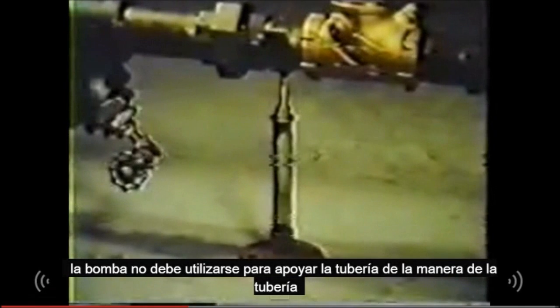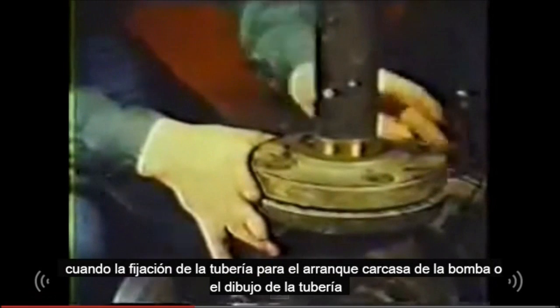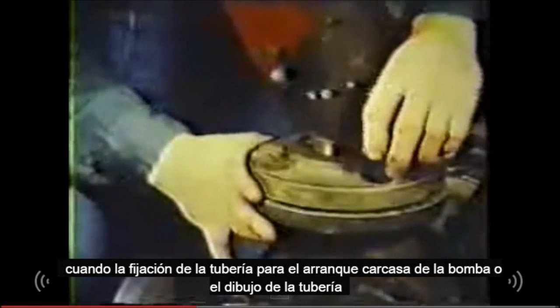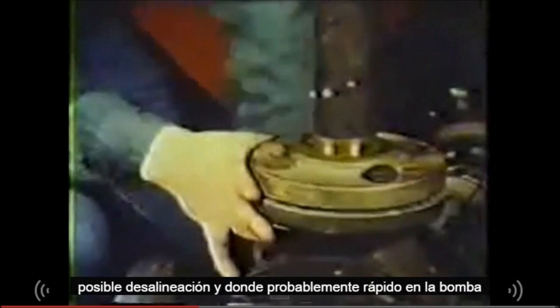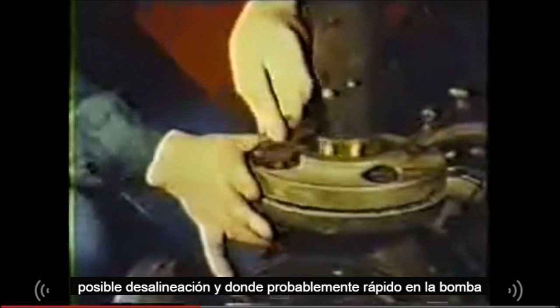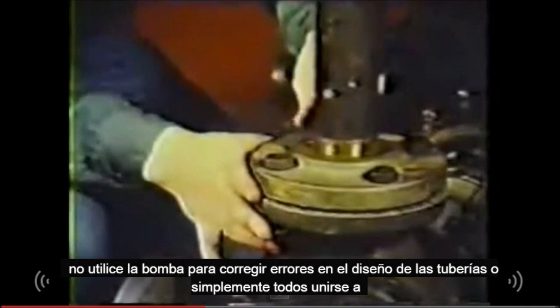The pump should not be used to support the piping. The weight of the pipe should be carried by hangers or other supports. When fastening the piping to the pump casing, springing or drawing the piping to the pump will cause distortion, possible misalignment, and probably rapid wear of the pump. Do not use the pump to correct errors in the piping layout or assembly. All joints of the piping system should be tight. Pipe dope or Teflon tape will help assure leak-free threaded joints. Leaks in the suction line permitting air to be drawn into the system may cause a noisy pump or a reduction in capacity.